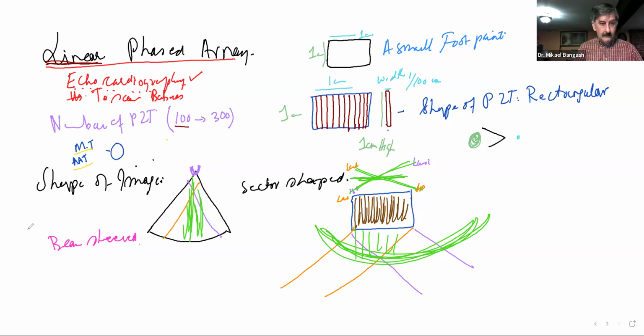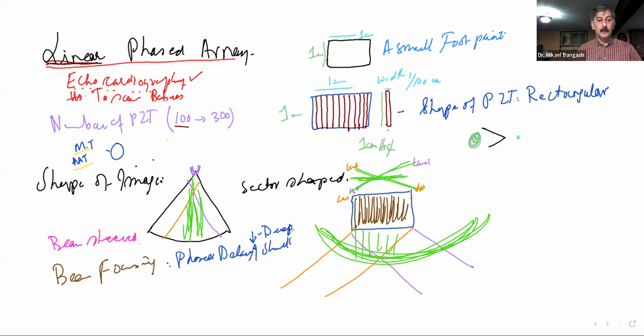Whereas at the same time, we have the beam focusing, which, as we just said, is all dependent upon what we call the phase delay. If we had a short phase delay, deep focus. Whereas if we had a great phase delay, we had a shallow focus. Now we can choose more than one focal point if we want to, or we can just choose one. Clear?